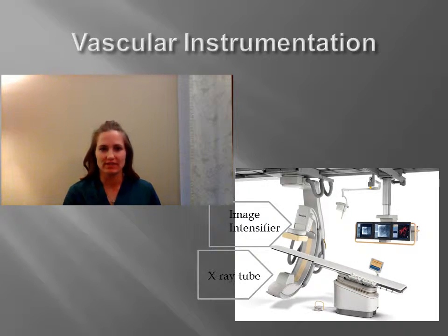Interventional imaging requires advanced radiographic and fluoroscopy equipment. This includes tubes that are attached to the ceiling along with a C-arm or an L-arm. Specific to interventional radiography, a small focal spot and a large anode disc are necessary components of the X-ray tube to accommodate for the increased heat load and to increase spatial resolution needed for imaging smaller vessels.